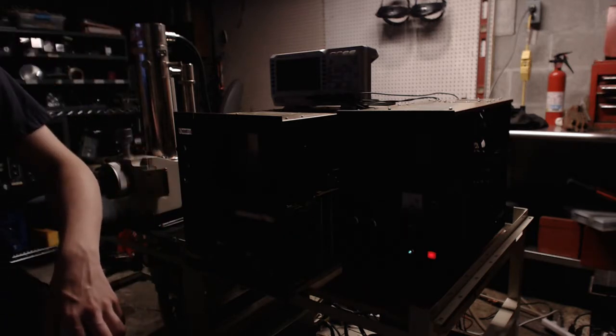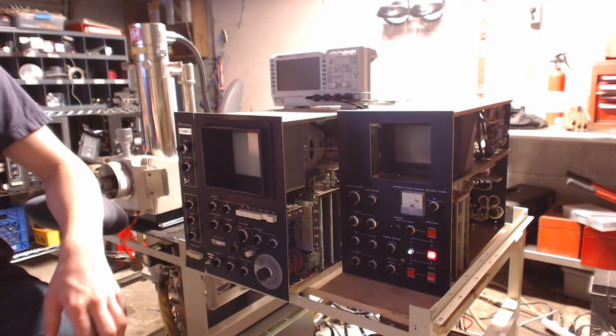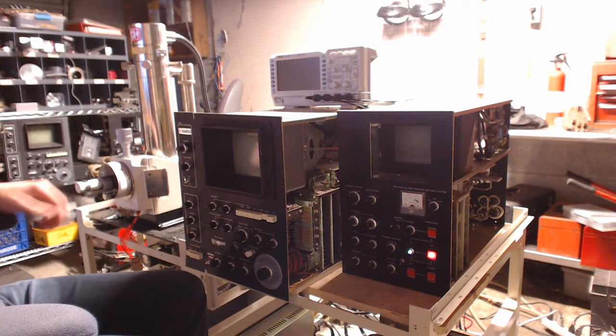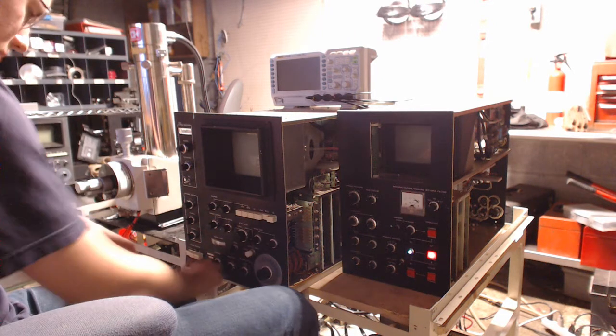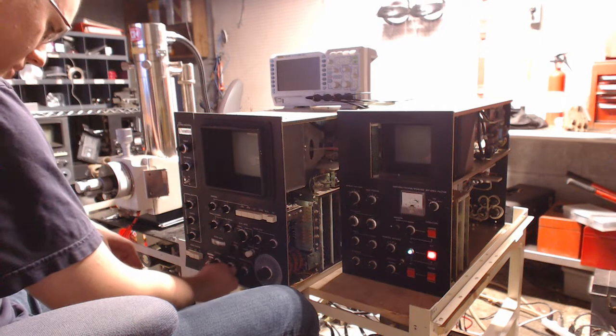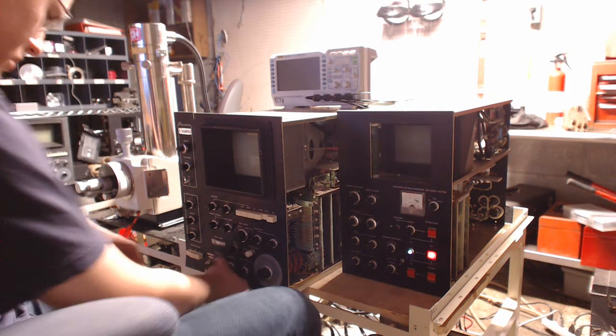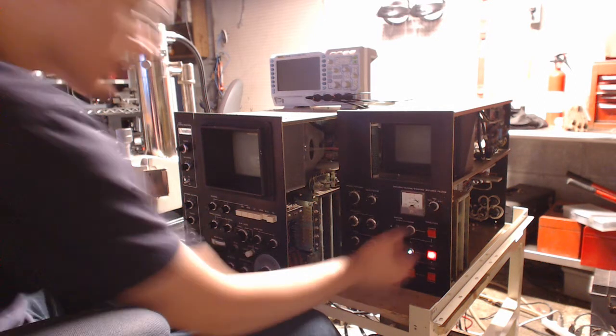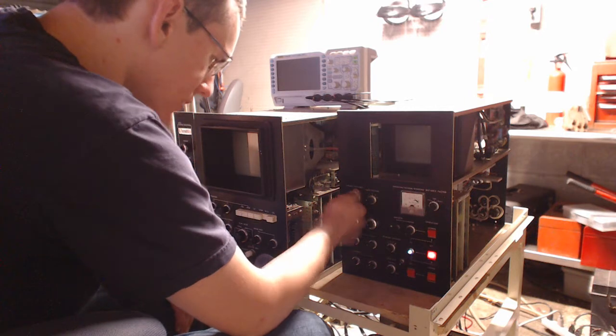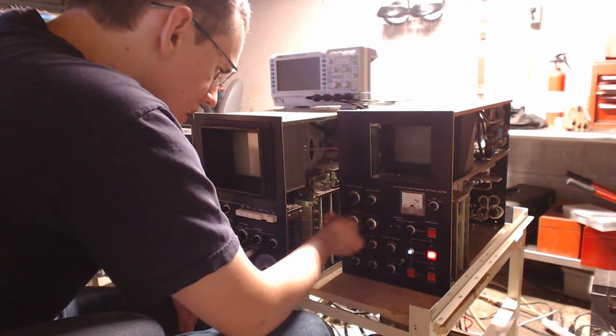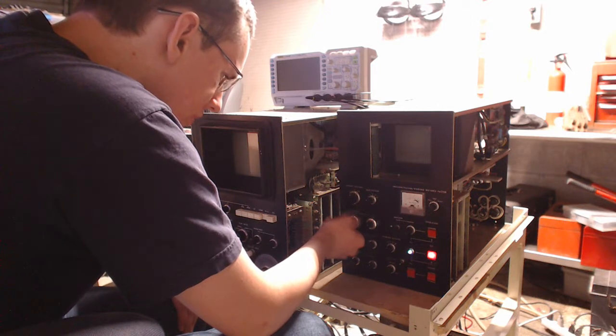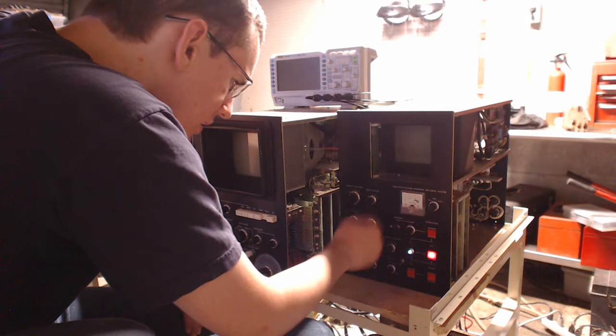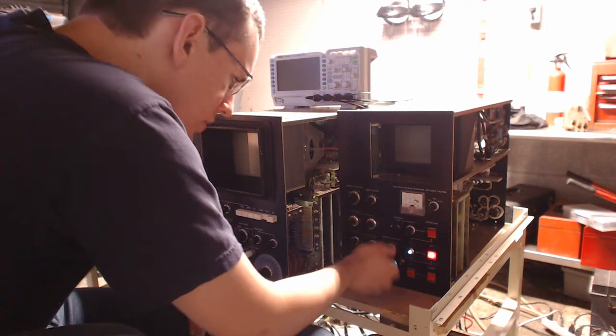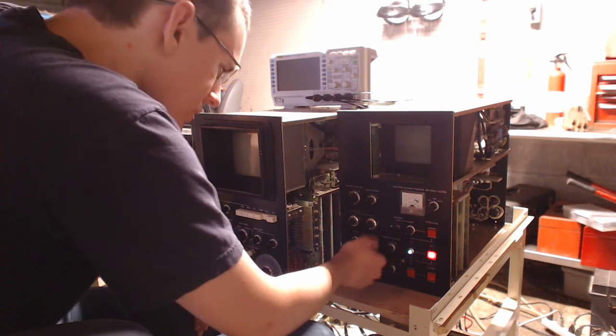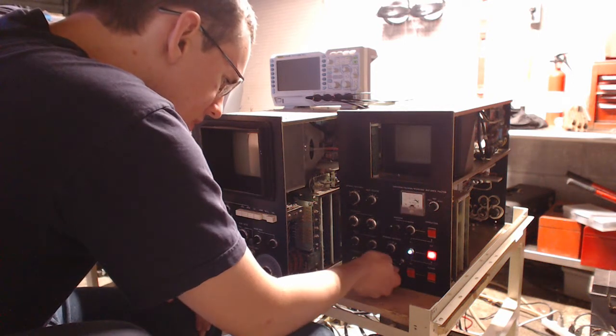Okay, here we go. Let me turn exposure up for everyone. Okay, we're in backscatter. Contrast is about zeroed out-ish. Brightness is low. Preamp is normal, current is down, high voltage is at 2 kV, dynamic focusing is off, stigmators need to be reset to 5.0 and 5.0. Working distance is correct. Alignment is reset. Spot size is correct.